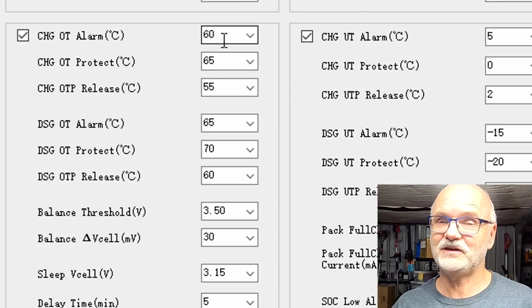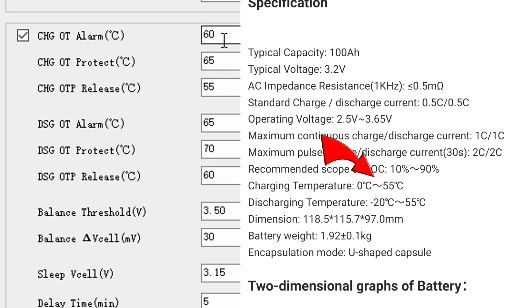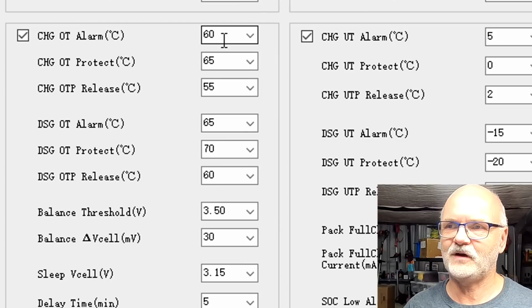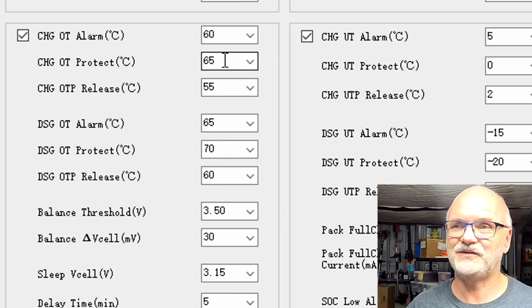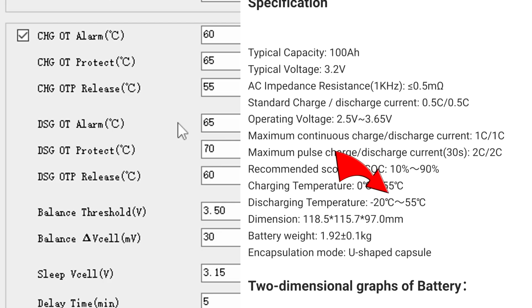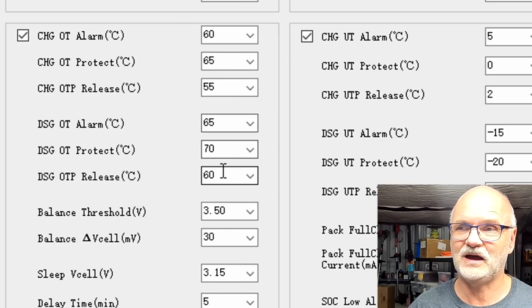Temperature alarm at 60 degrees. Again, here from the specifications, it says 55, so this one is far too high. And the protection kicks in at 65. Again, far too high, 10 degrees too high. Discharge temperature, as per specifications, 55 degrees. These settings are too high as well.